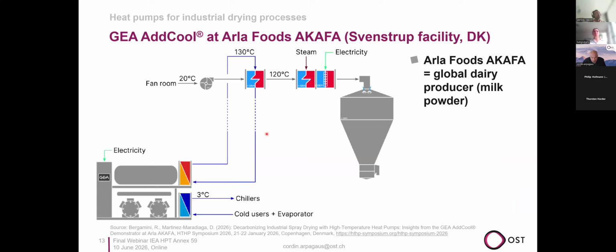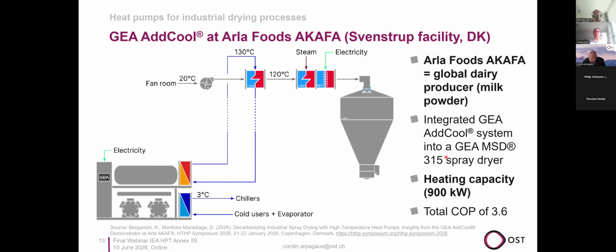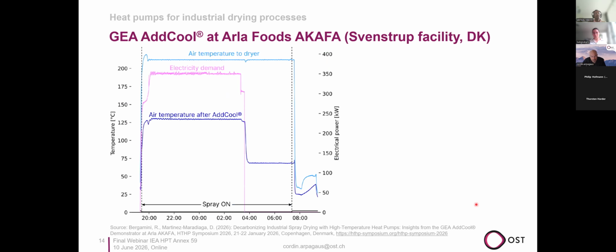So the principal concept is similar. We have here the CO2 heat pump, the cooling loop for the chillers, which can be used for cooling, and then the air heating up to 120 degrees with the CO2 technology. Then later on, steam or electrical heating for further upgrading the heat to maybe 200 degrees. So this has been integrated in this MSD 315 spray dryer, 900 kilowatts capacity, COP of 3.6. What is interesting is that this heat pump can react very quickly.